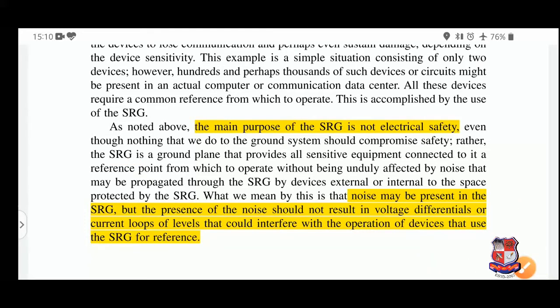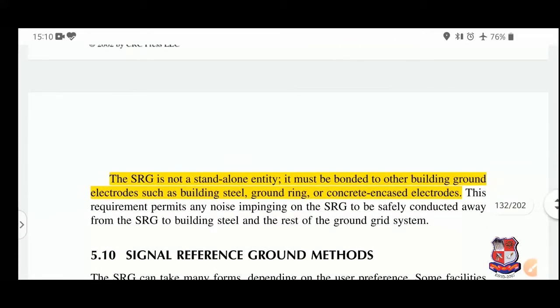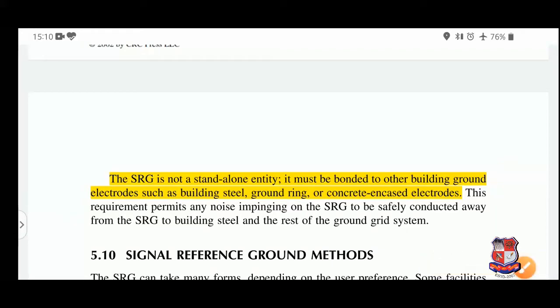The benefit of keeping the SRG as a low-impedance level is that it will contain the noise within itself and not transfer it to the communication devices — sending and receiving. The SRG is not a standalone entity. It must be bonded to other building ground electrodes such as building steel, ground ring, or concrete-encased electrodes. This requirement permits any noise impinging on the SRG to be safely conducted away to the building steel and the rest of the ground grid system.